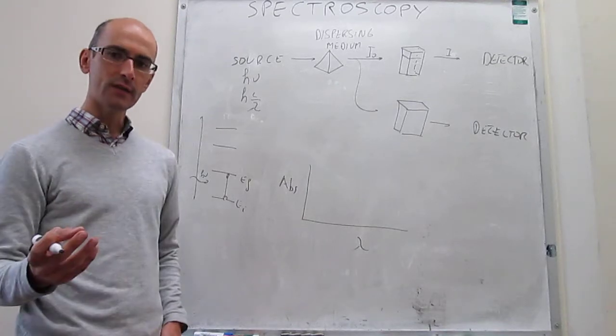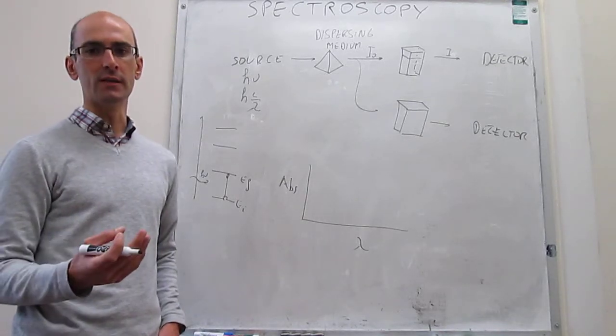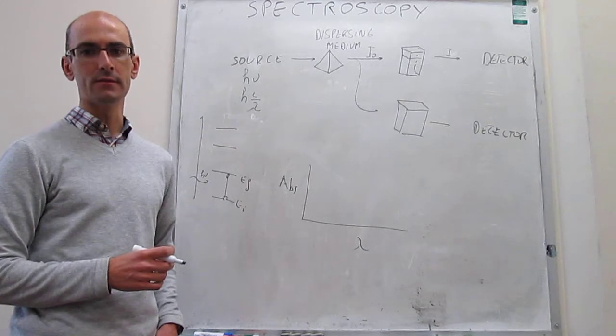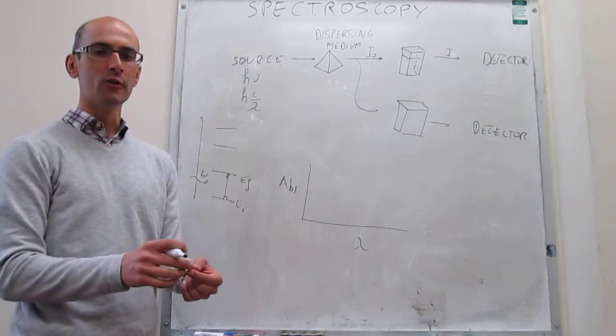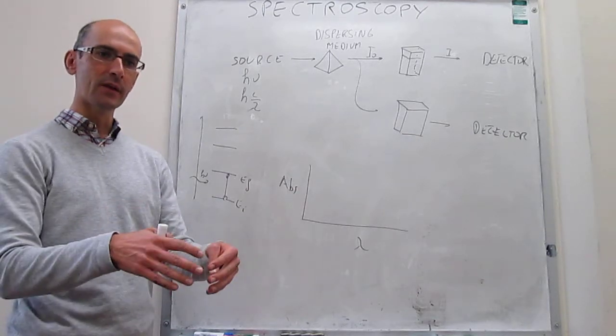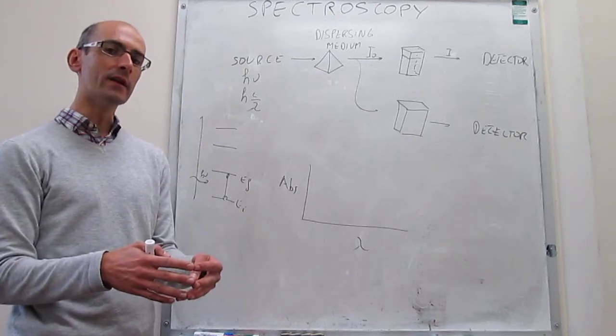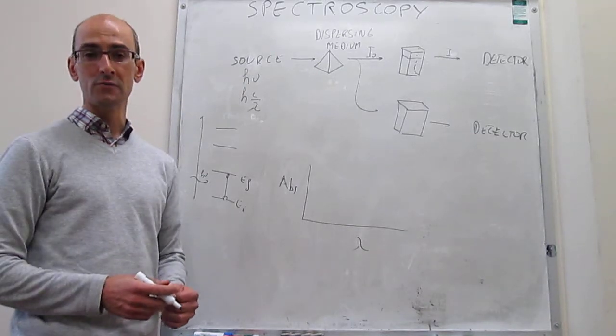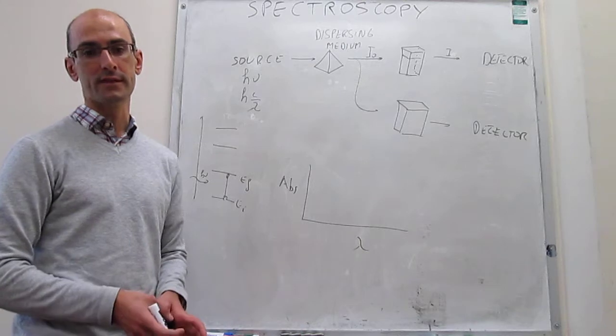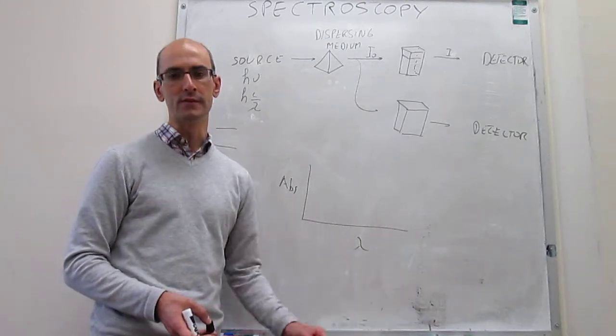Your source, usually in UV-vis, is going to be a hot filament, or you're going to have a deuterium or tungsten lamp. In the case of a tungsten lamp, it will be a hot tungsten filament that by the black body radiation process actually emits photons in a broad range of wavelengths, covering all the way from the ultraviolet to the visible.